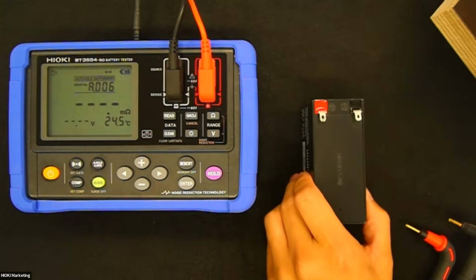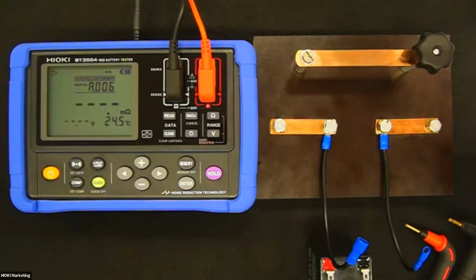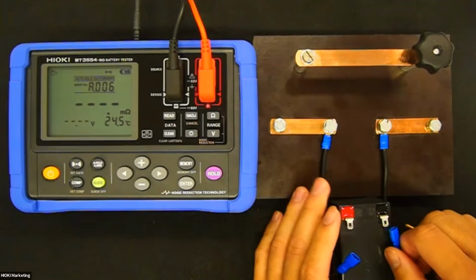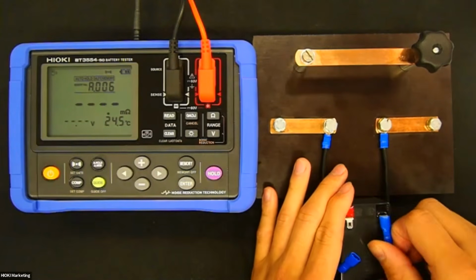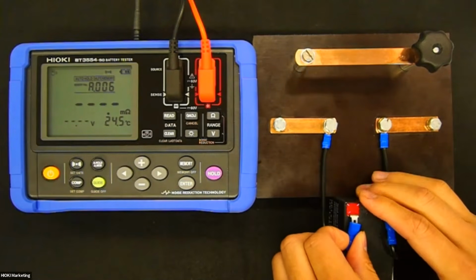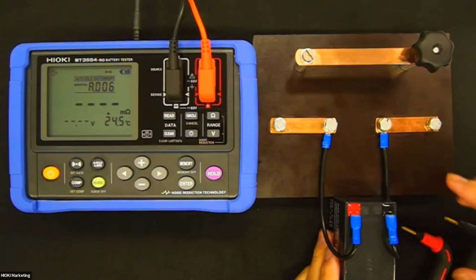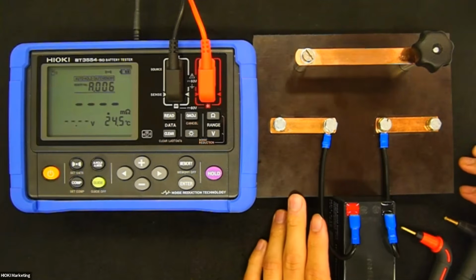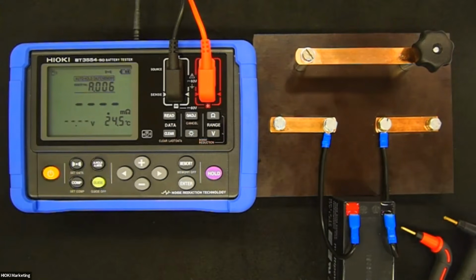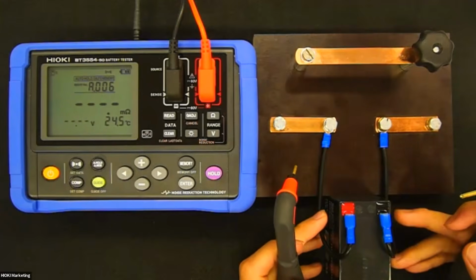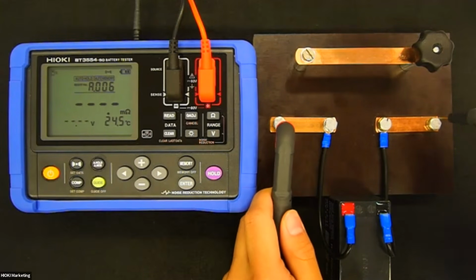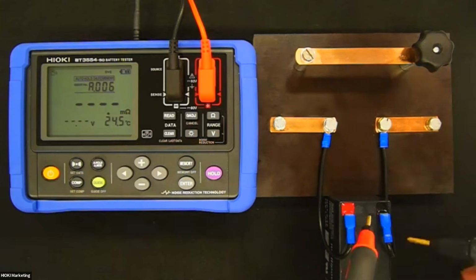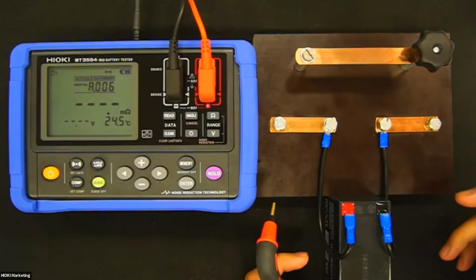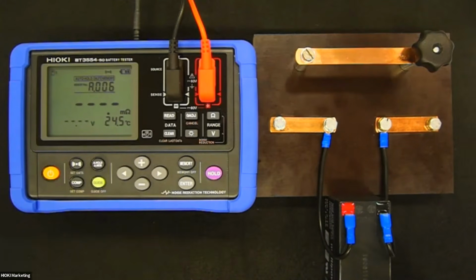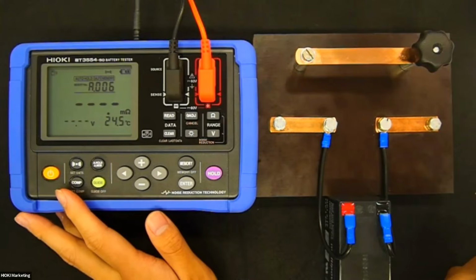Now I want to show another tip for measurement. This is a dummy bus bar. In an actual UPS, these bus bars are used to connect the batteries to each other. When you check battery health, you have to make contact from the bus bar, not directly on the battery terminals. Now I can show you a judgment example using our comparator functions.